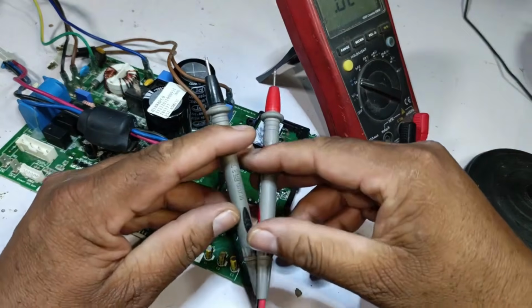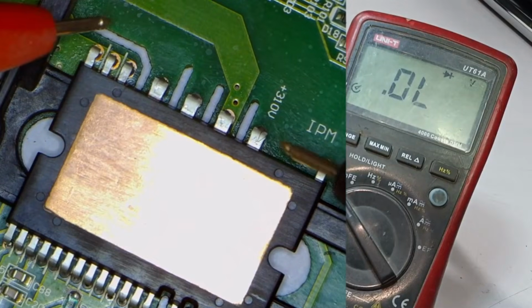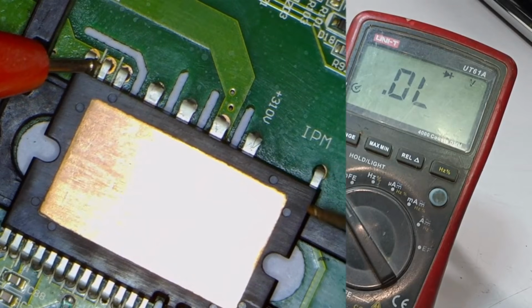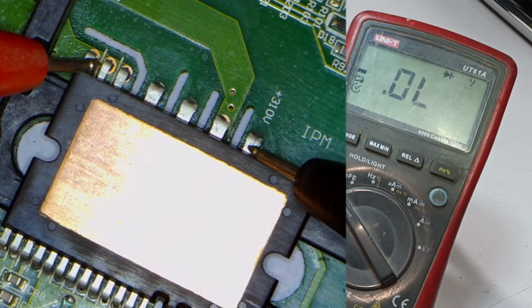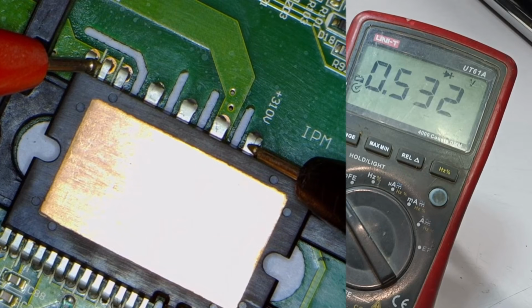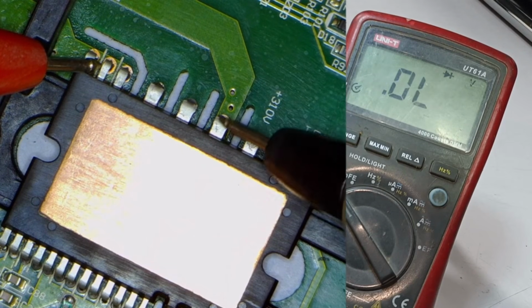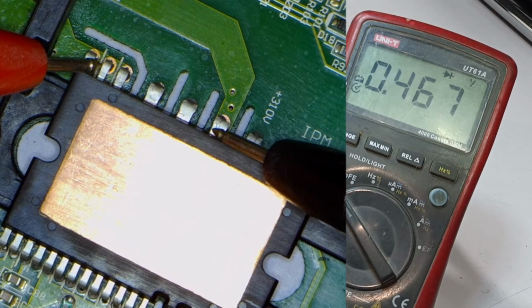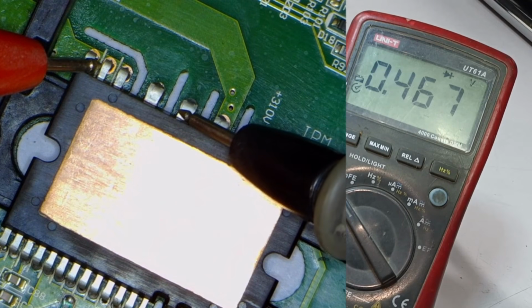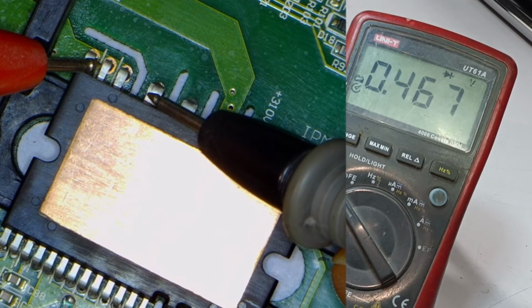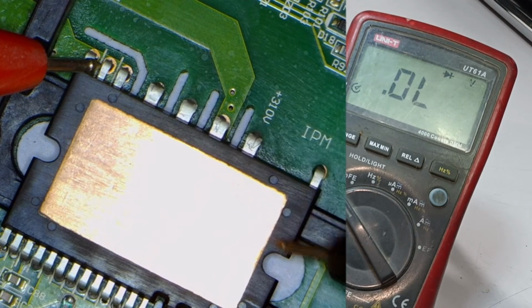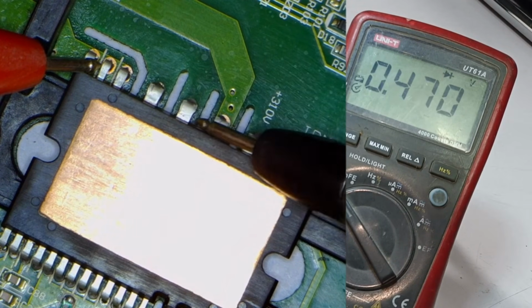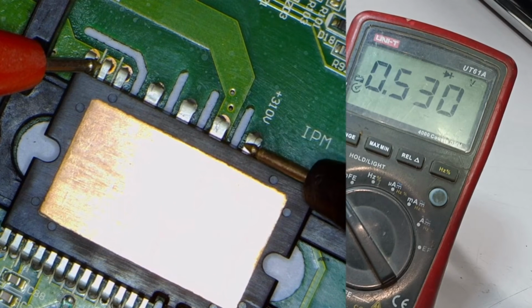Now I will switch the probe sides, placing the positive probe on the negative pin and the negative probe on the positive pin. Let's see what happens. We now observe a voltage drop of 0.532 here. Let's check the U point in the same way — there is a 0.467 voltage drop here. The same 0.467 voltage drop is observed on the V pin and also on the W pin. This means all these points are fine, which indicates the IPM is perfectly okay.